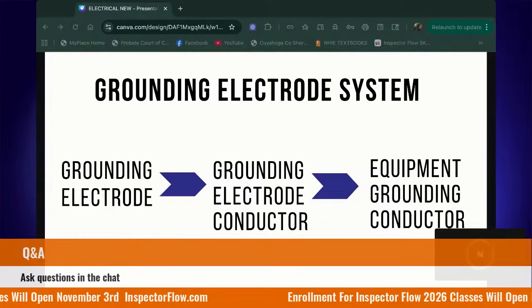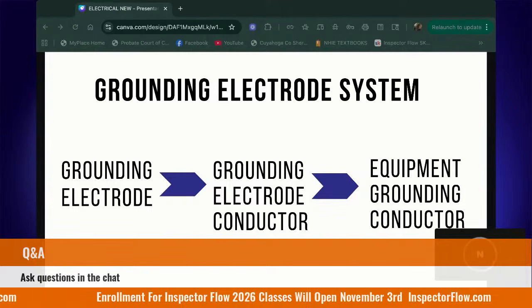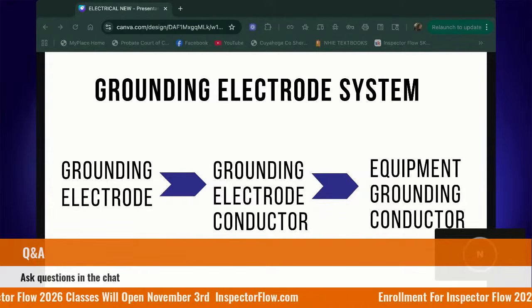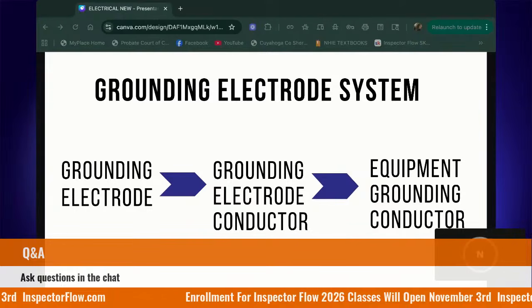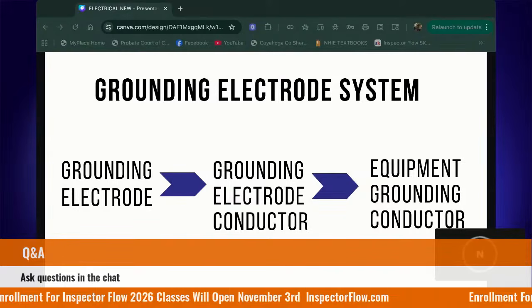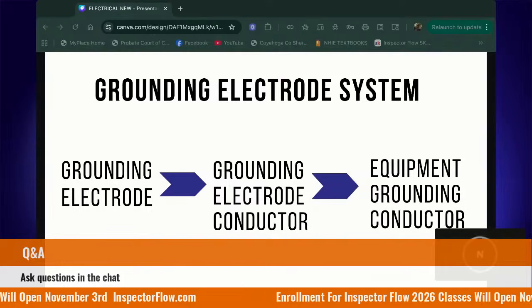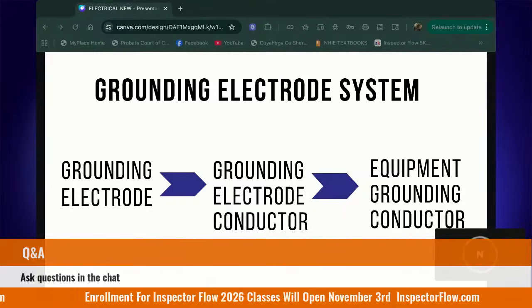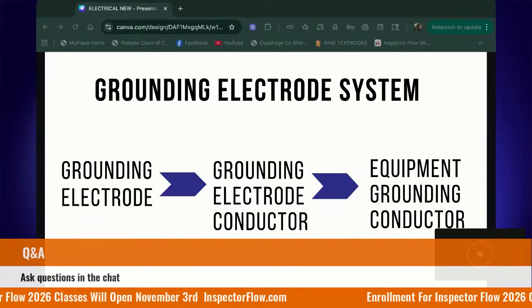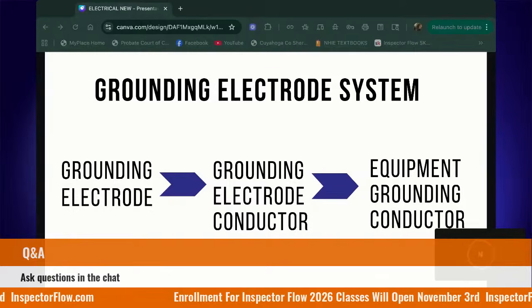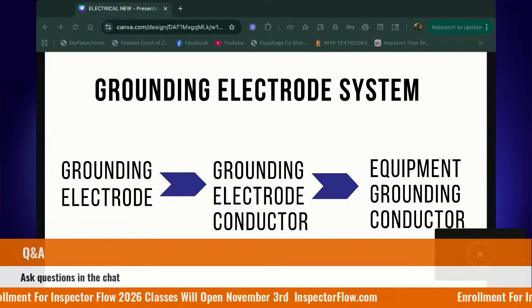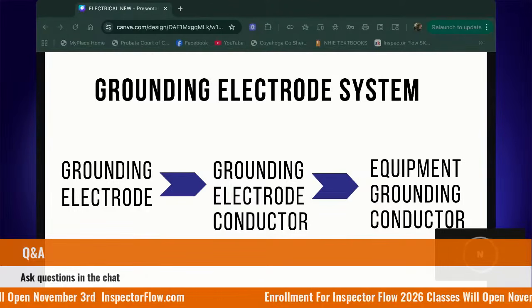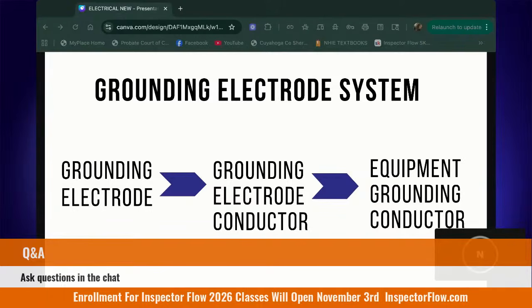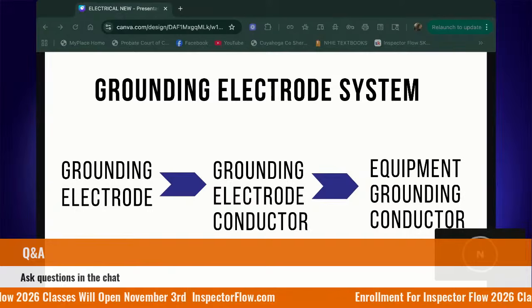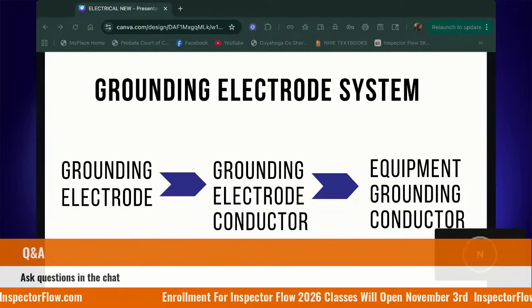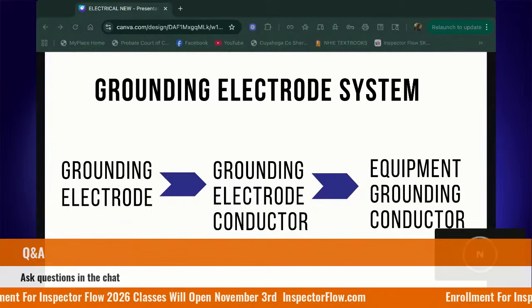Okay, so the last thing with our grounding system is our grounding bus bar in the panel. Remember, we just saw a neutral bus bar. Well, we can have a grounding bus bar as well. Again, it's just a metal strip inside the main panel where all the grounding wires connect. So if I'm looking at a panel, how will I know if I have a neutral bus bar or a grounding bus bar? The wires. Green and copper wire. The grounding will be copper. The neutral wires will be white. That's correct. If I see a bus bar with all white wires terminating, I know this is my neutral bus bar. If I see a bus bar with all green or bare copper wires terminating, I know this is my grounding bus bar.